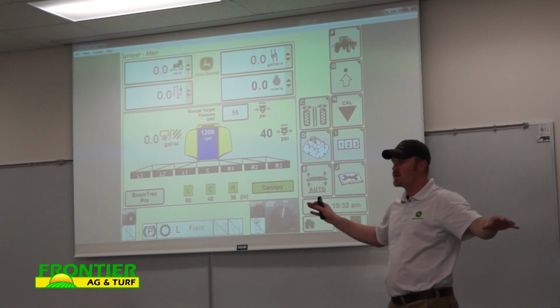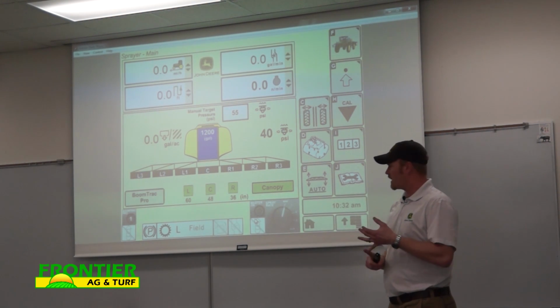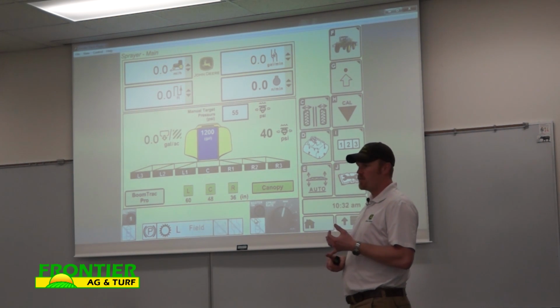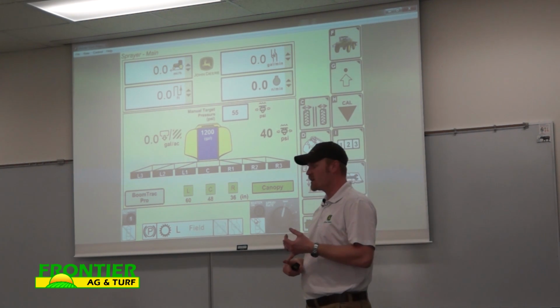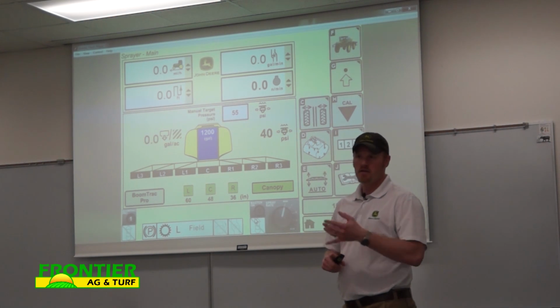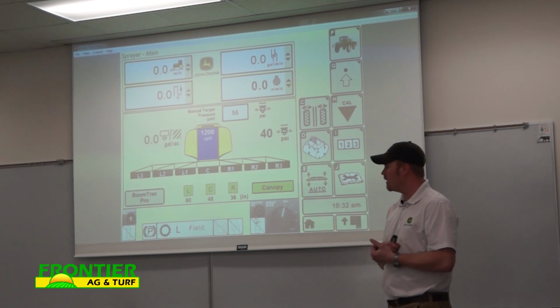If it starts dancing, we've got to take a look at a few things. One, the calibration of the sensors — you can't just plug them in and go. There are serial numbers and calibrations you have to enter in the display. Dennis, you're probably pretty familiar with that.